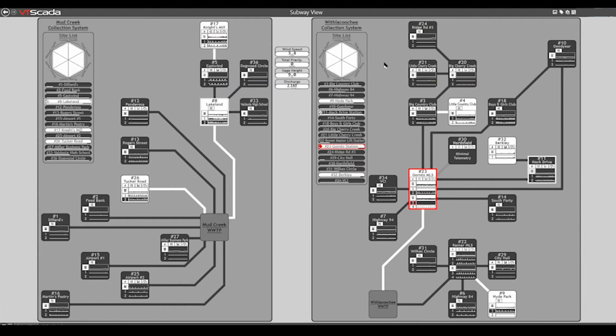We always have people say they want accuracy. We say, well, accuracy is important, but you can calibrate for accuracy as long as things are repeatable. What we want to show them is that the system's healthy and everything is repeating like it should. When you see a deviation from that repetitive performance, then you have to start paying attention to it.